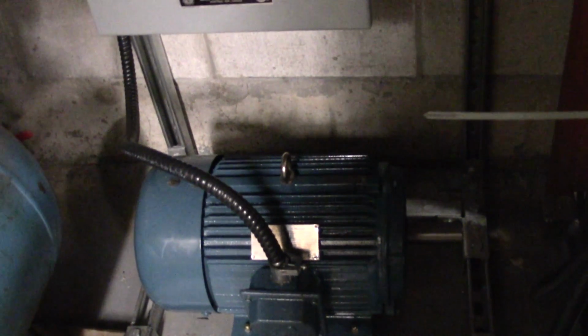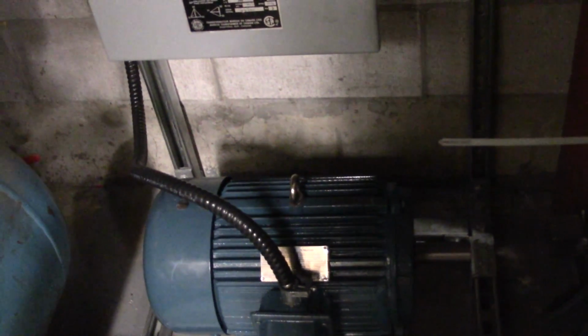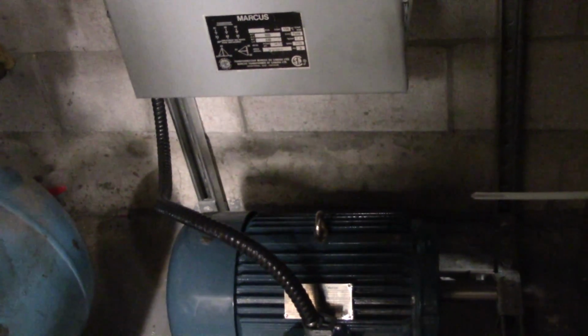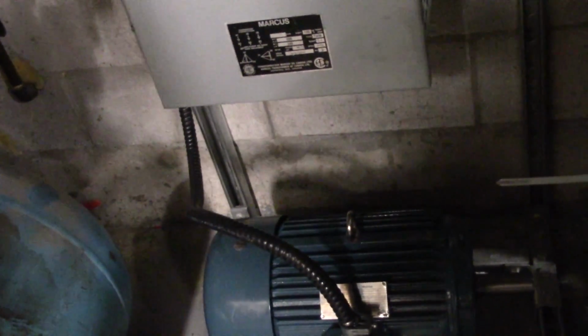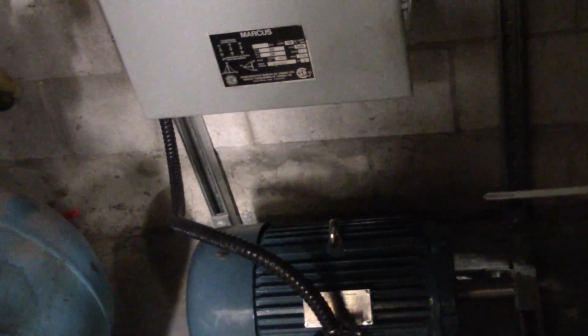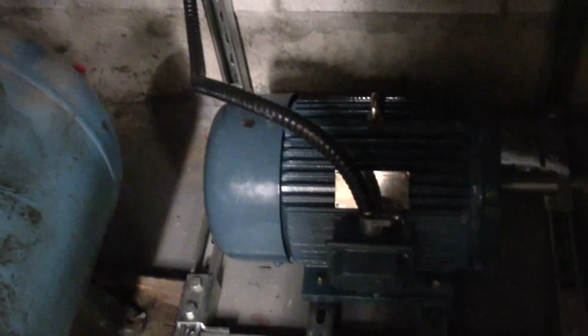And how this phase converter works is the motor creates that third phase out of the single phase that you get from your city, which is 120, 240. And together that brings your voltage on 3 phases instead of single phase. So that's about the sound. That's what it should sound like, and it's running pretty smooth. Okay, we're going to close the breaker for the transformer, and you can hear a slight hum from the transformer. That's 240 to 600. So let's go over by the mill and we'll fire it up.